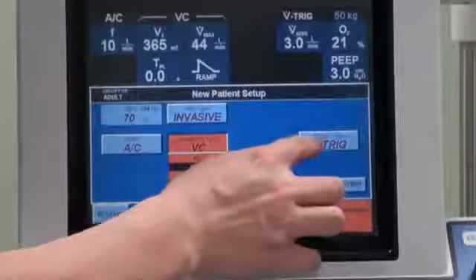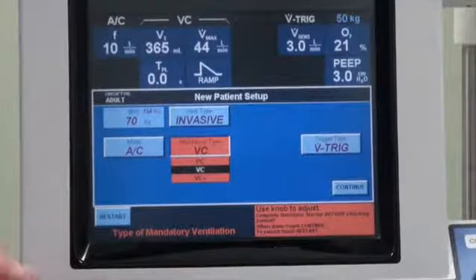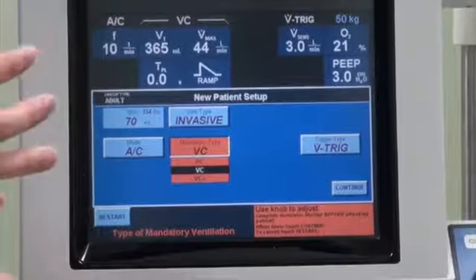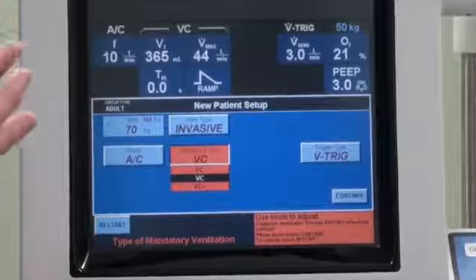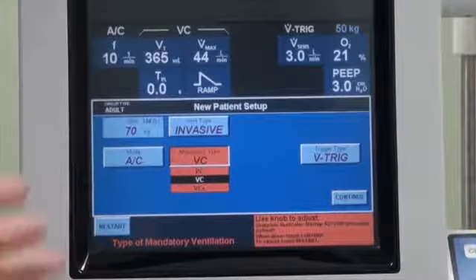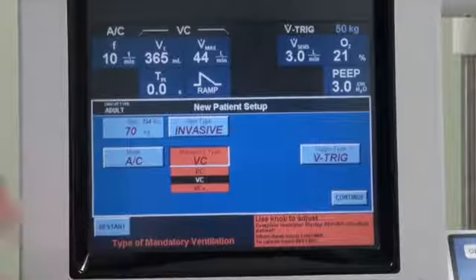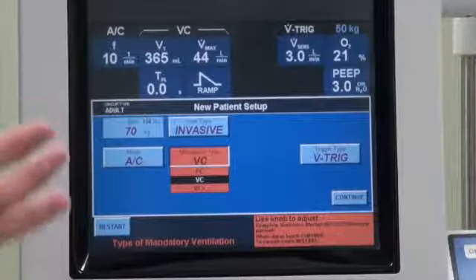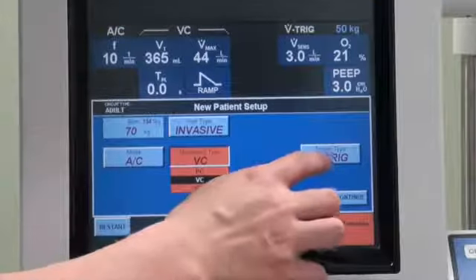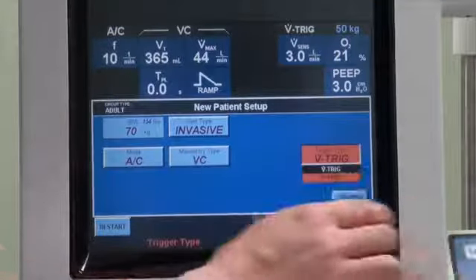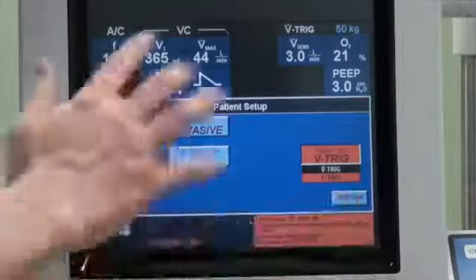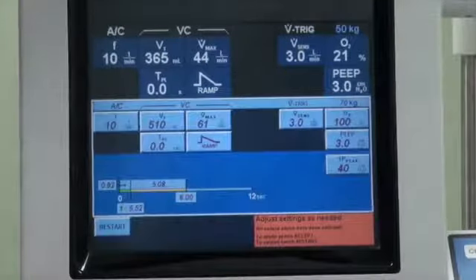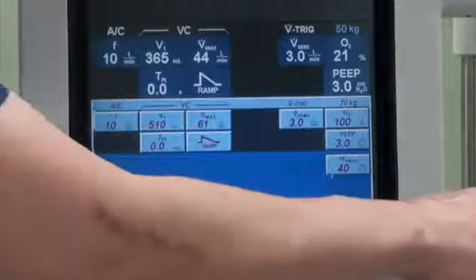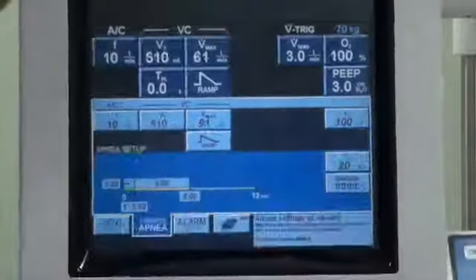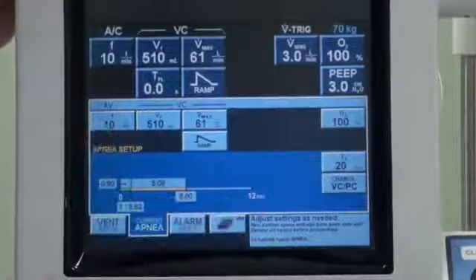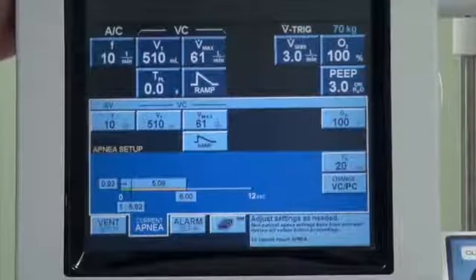The next button that they will ask you to determine is the trigger. Trigger is how the ventilator will be able to detect that the patient is taking a breath, and this can be either through changes in the flow or changes in the pressure. For this particular setting, we will just choose a flow trigger. Once you have selected, you just press confirm, and if you want to finalize your option, you just need to press accept.